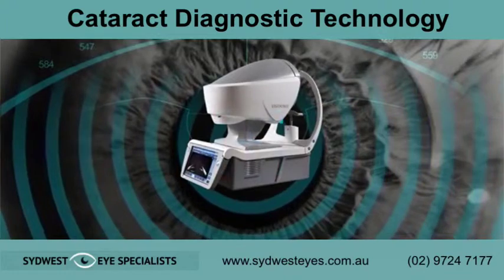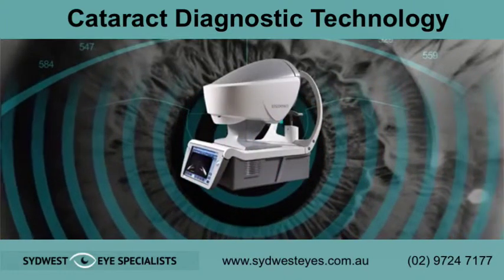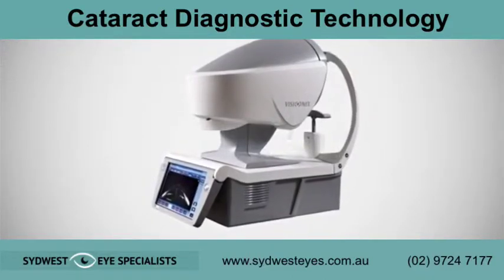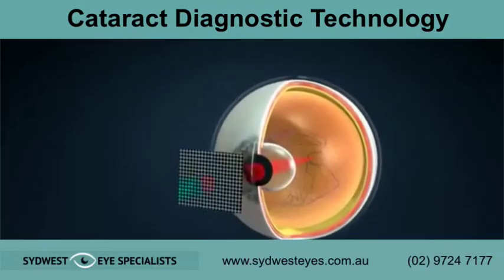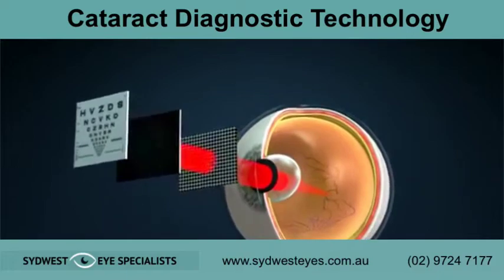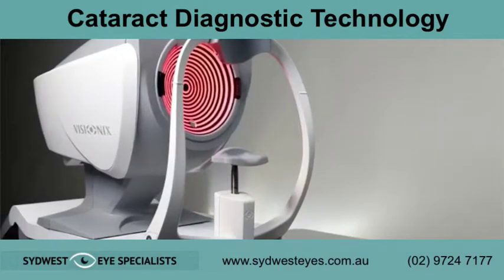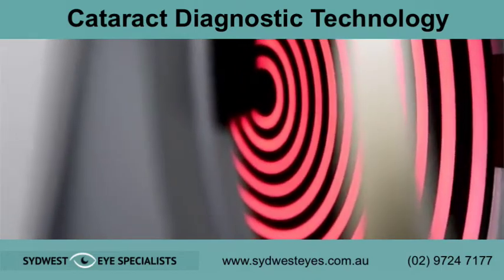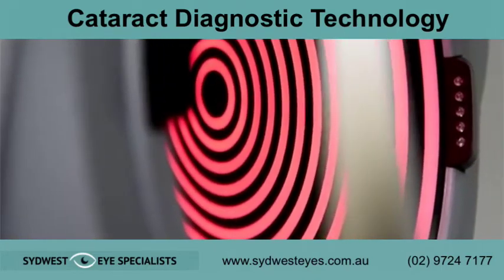Visionix, the pioneer in wavefront technology, once again sets the innovation standard. The VX130 Plus is a fully automated instrument which obtains a complete anterior segment analysis of both eyes in less than two minutes. You can use this machine either to perform complete examinations of the anterior segment of the eye or specific examinations.